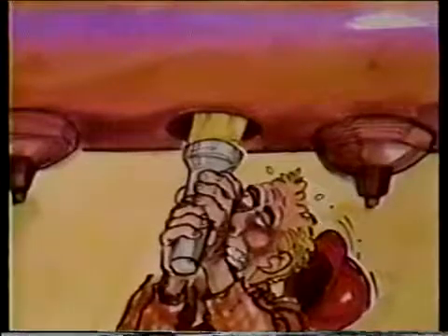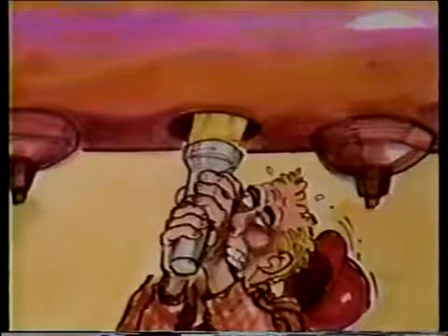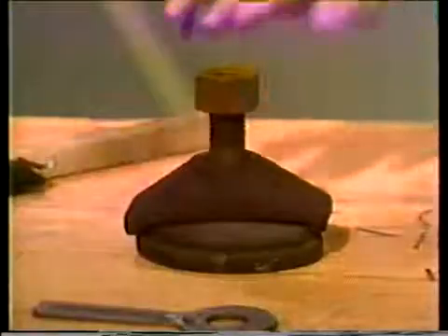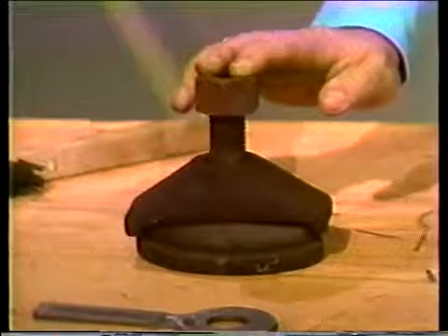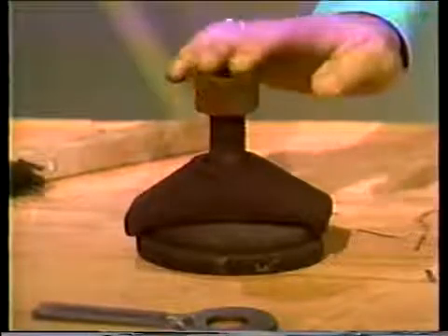Handholes are small header openings intended to provide access for inspection. Now, handhole plates cover the handhole openings. Only headers with gasketed handhole plates are easily accessible. Now, some handhole plates are welded to the header and are usually very hard to remove. These difficulties normally prevent examination of most of the waterside surface and make it doubly important for you to examine the available portions of the waterside very closely. You can't afford to overlook any potential problem.